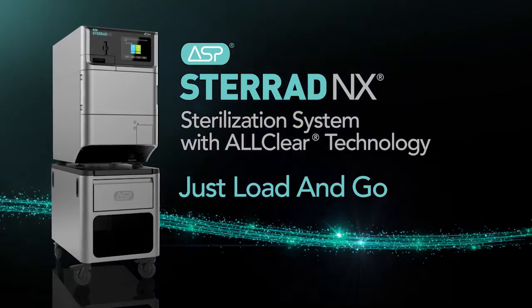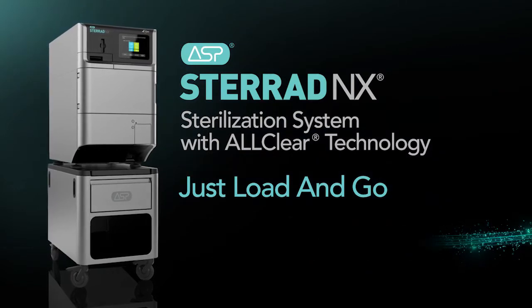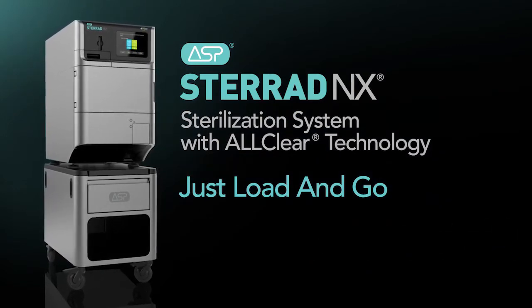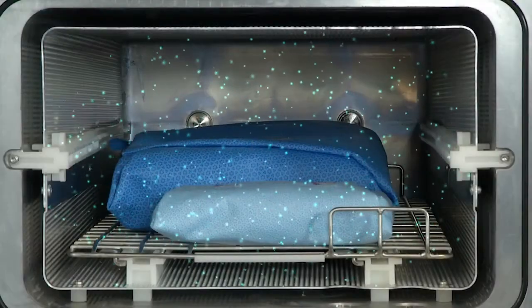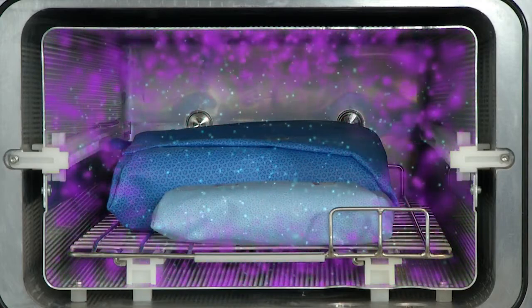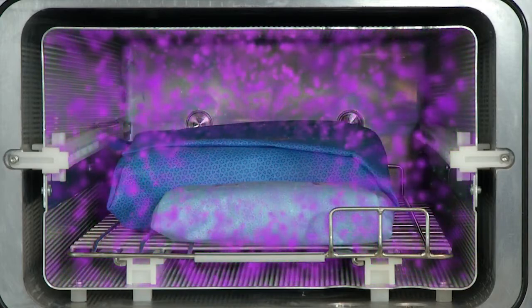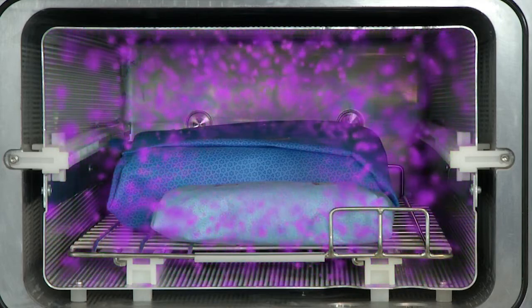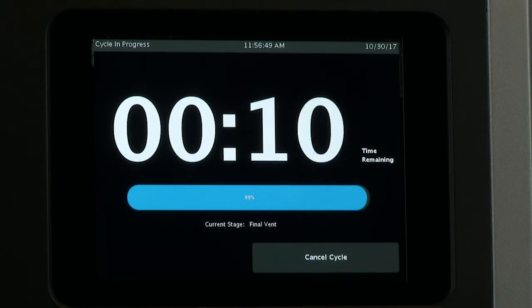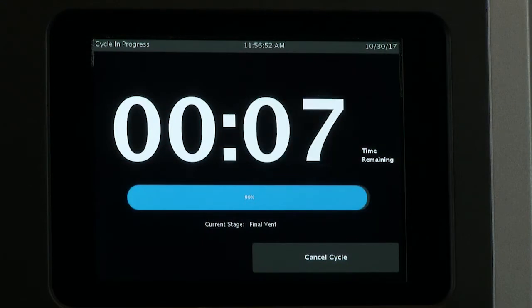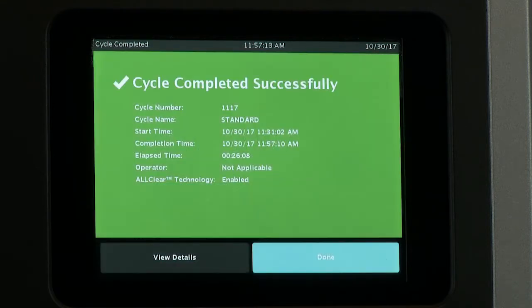The STERRAD NX sterilization system with ALLClear technology is a general-purpose, low-temperature sterilizer that sterilizes medical devices by diffusing hydrogen peroxide vapor into the chamber and then electromagnetically exciting the hydrogen peroxide molecules into a low-temperature plasma state. The combined use of hydrogen peroxide vapor and plasma safely and rapidly sterilizes medical instruments and materials without leaving a toxic residue. All stages of the sterilization cycle operate within a dry environment at a low temperature, and thus the cycle is not damaging to compatible instruments that are sensitive to heat and moisture.